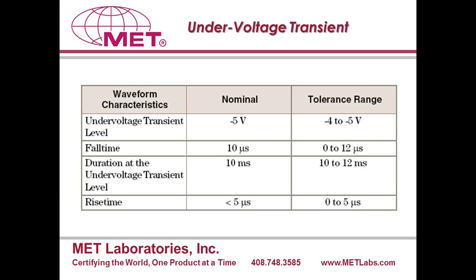However, the standard clearly defines the options of using a transformer or inductors to tackle that situation, rather than using the resistive circuitry or resistive network for currents higher than 25 amps. So I'm not going to focus on the impulse. My main focus will remain on the undervoltage and overvoltage.